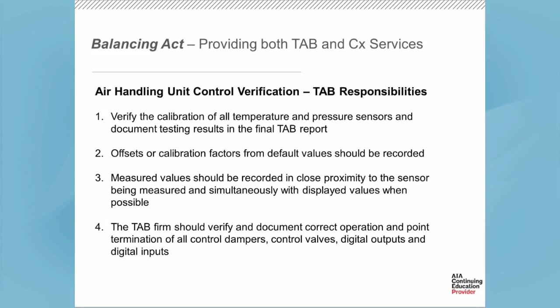So this isn't just temperature sensors and pressure sensors and flow sensors and things of that nature. It's making sure that control dampers operate correctly, making sure valves operate correctly, making sure that start-stop signals control the appropriate VFDs or other starters and devices. A whole myriad of things, but just those simple inputs and outputs we find is best for the TAB firm to verify in preparation for functional testing, which would be conducted or at least facilitated by the commissioning provider. Also, testing the safeties, as we talked about, especially high and low static pressure switches and things of that nature.